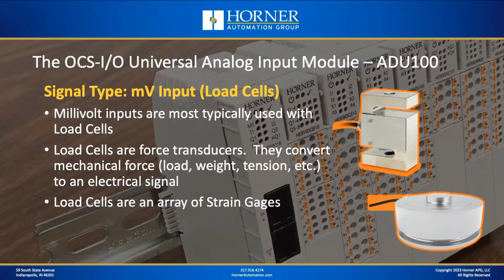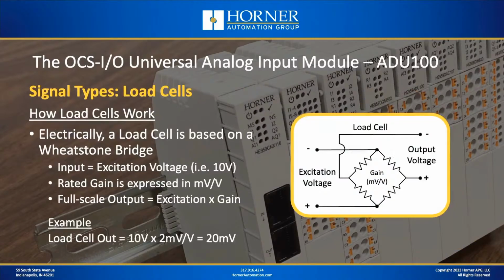Sometimes you'll hear the term strain gauge being used. Well, strain gauges are actually internally part of the construction of the load cell. A load cell is actually an array of strain gauges. Now let's dive a little more deeply into how load cells work. So electrically, a load cell is based on a Wheatstone bridge. And all those little resistors you see there, those are effectively strain gauges, individual strain gauges.